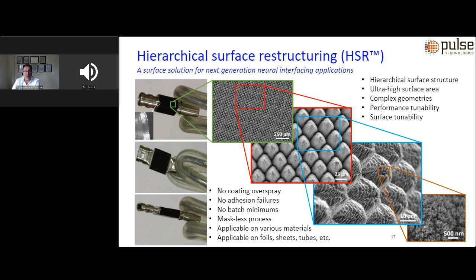So here I'm showing some examples of real-world electrodes that have been restructured using our patented HSR technology. From top left, you will see a cylindrical platinum iridium electrode for cardiac pacing applications. Then next to that, you see a helix platinum electrode, again for cardiac applications, a helical electrode, a rivet-style platinum iridium electrode for an electrophysiology mapping catheter. Then next to that is a cylindrical platinum iridium electrode for use in a percutaneous spinal cord stimulation electrode array. And then to the very right is a flat electrode that is used in a paddle lead spinal cord stimulation electrode array. All of these are examples of real-world devices that we've worked with many customers and developed for them.